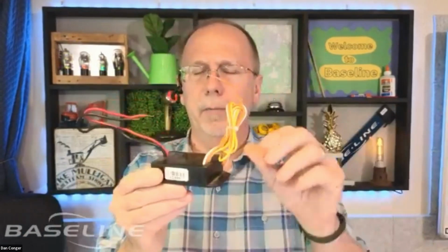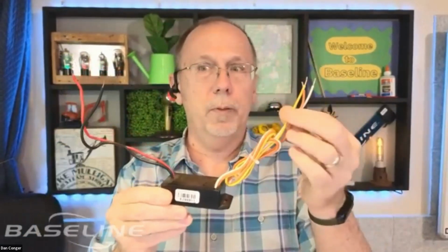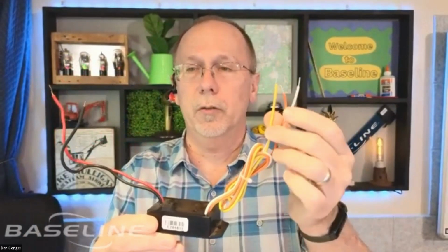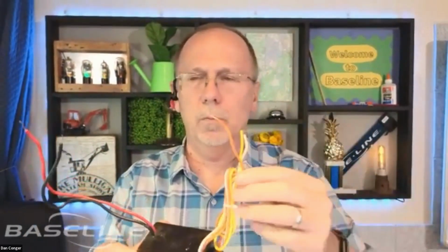So here we got a decoder. And so what we're talking about, this is the 2-wire side. This connects onto the 2-wire path, and this is the solenoid side. So open circuit solenoid, short circuit solenoids, that's all on this side of the problem, right? So what do you think might cause an open circuit solenoid? Any ideas, Tracy? Could be a bad solenoid. So the solenoid could be bad.